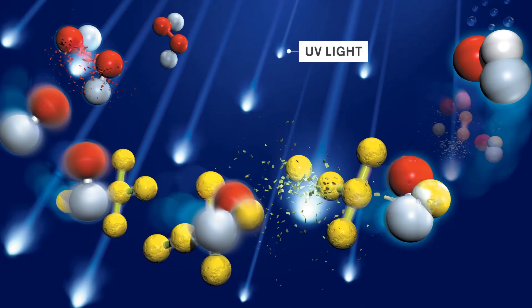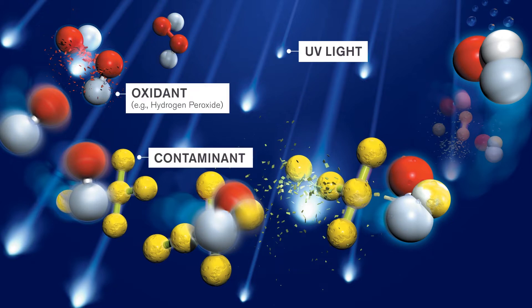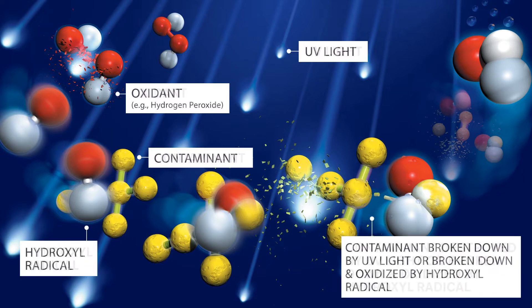When UV light traverses water, it can be absorbed directly by targeted chemical contaminants and by the specific oxidant added to the water, resulting in the breaking of chemical bonds. Contaminants are either broken down directly by the UV light, or the UV light-absorbing oxidants generate powerful radicals that rapidly interact with and oxidize them.